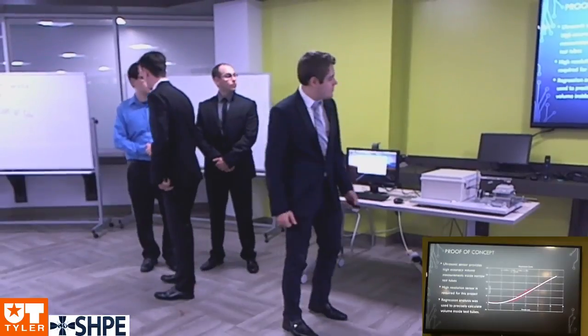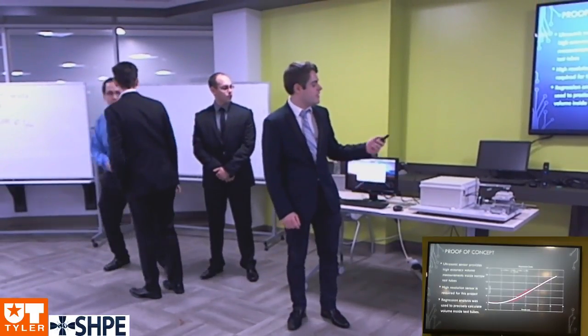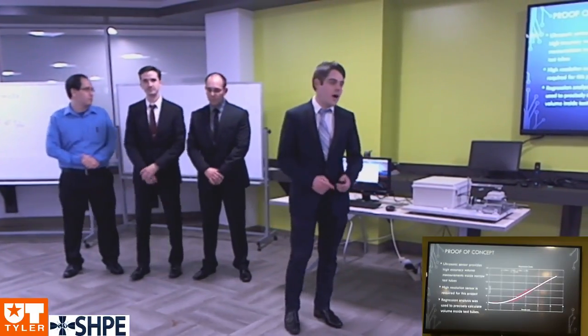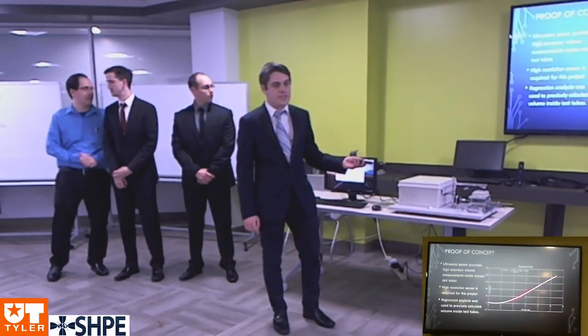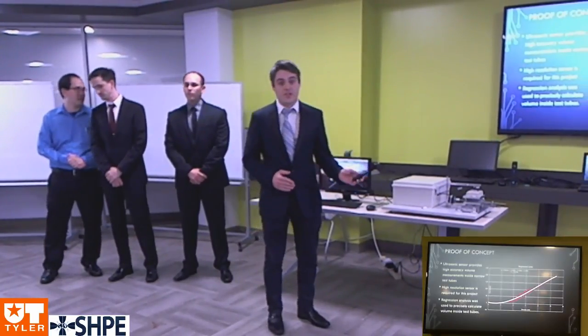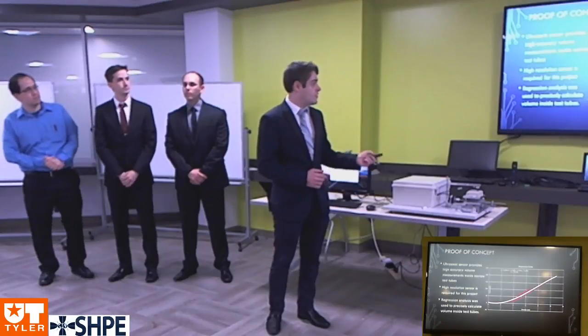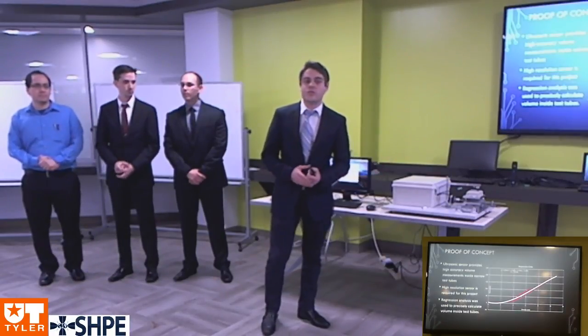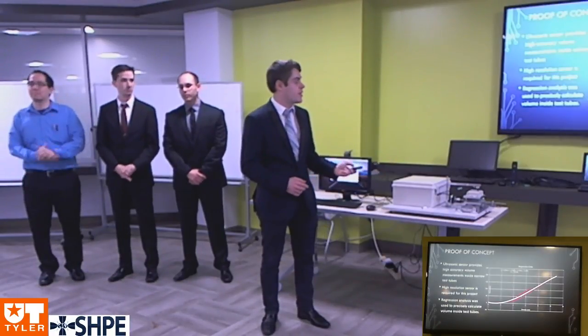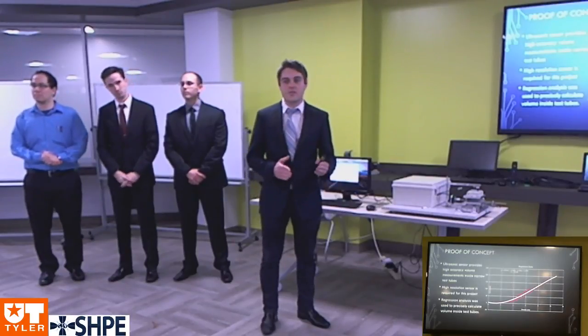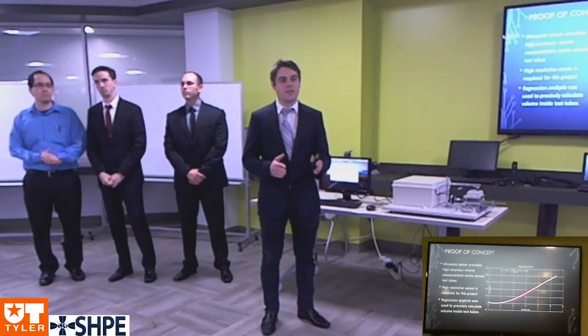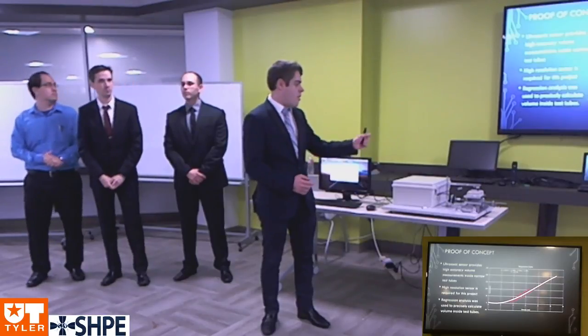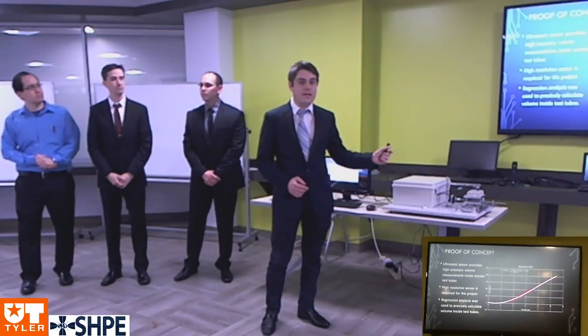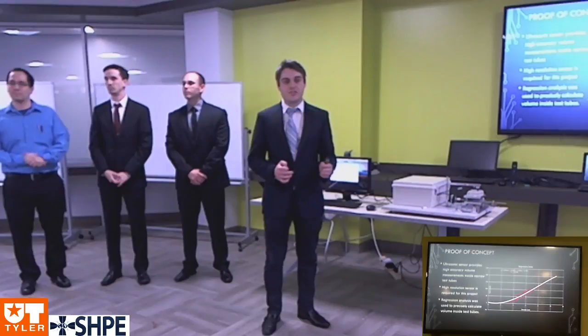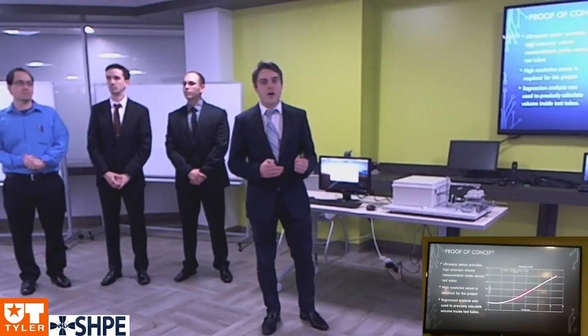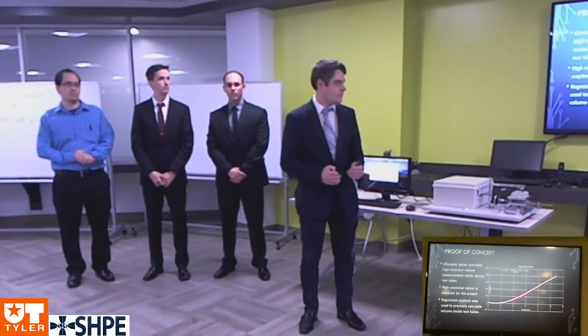One of the crucial aspects of this project is the accuracy that the workstation is able to provide. This project employs the ultrasonic sensor that is able to provide such accuracy measurements. The ultrasonic sensor features a resolution of 0.056 millimeters or 56 micrometers, which means that the sensor is able to detect a change of distance as small as 56 micrometers. When translated to the volumes inside the test tubes, under ideal conditions, the sensor is able to detect a change of 2 to 4 microliters.